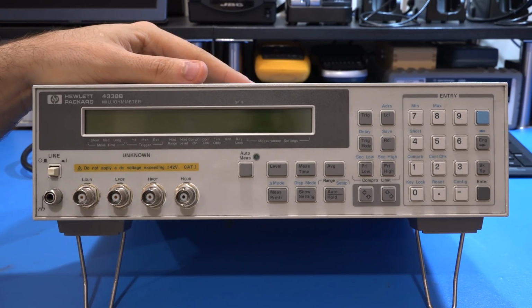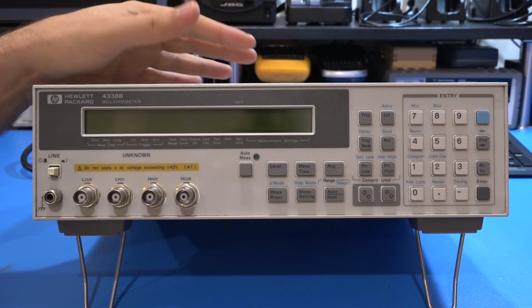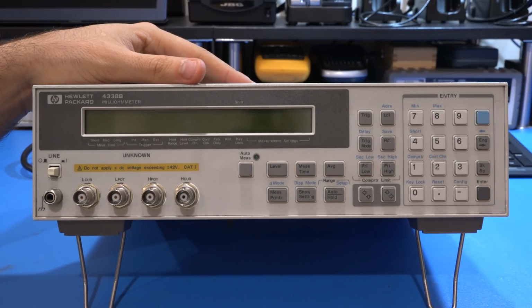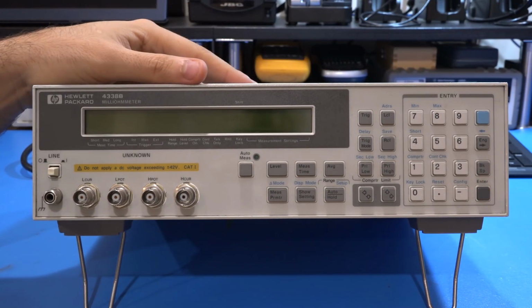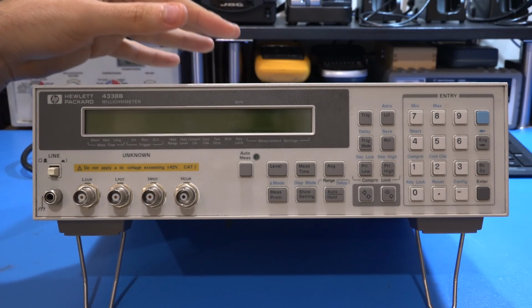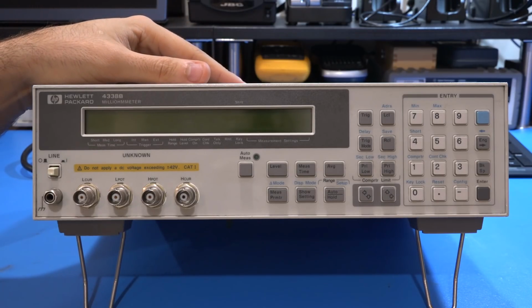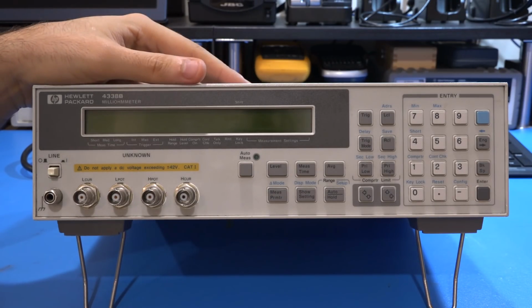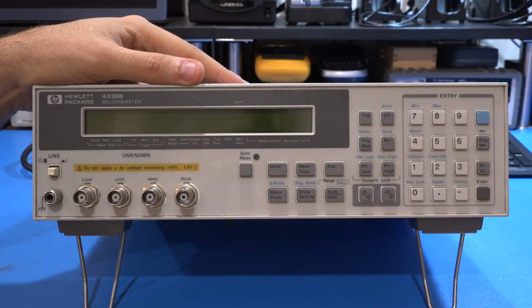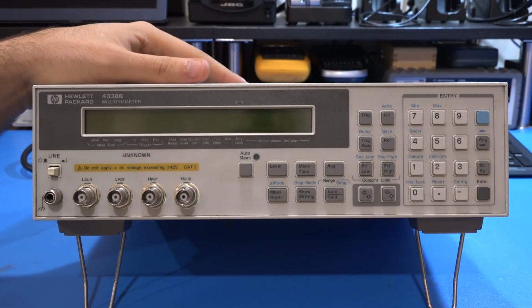Now this milliohmmeter can measure as little as 10 micro-ohm and as high as 100 kilo-ohm, which itself is really quite wide. And you may ask, well, what's so special about a milliohmmeter? Why can't you just use a 7.5 digit meter or an 8.5 digit meter you have to measure that? Well, in theory you can, but there are differences. First of all, this measures the resistance at 1 kilohertz. And the other thing this does is that you can control very precisely how much current this puts into your device under test. And it can be as small as 10 microamp all the way to 10 milliamp, or even maybe down to 1 microamp.